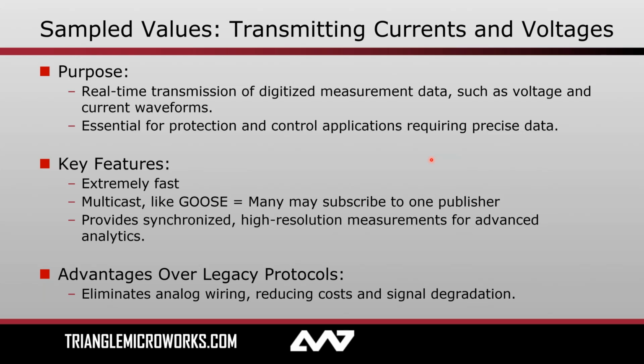Also, synchronization is something that comes up a lot with sampled values. Let's say that I need to subscribe to a sampled value stream from 2 different points in my substation. Therefore, I have 2 different IEDs measuring and sampling the voltage and current there and publishing it. I need to be able to compare apples to apples to know that a message that came from one was sampled at the exact same point as a sample that came from another if I want to do something like differential protection. And we do that via a synchronization method via a grandmaster clock.